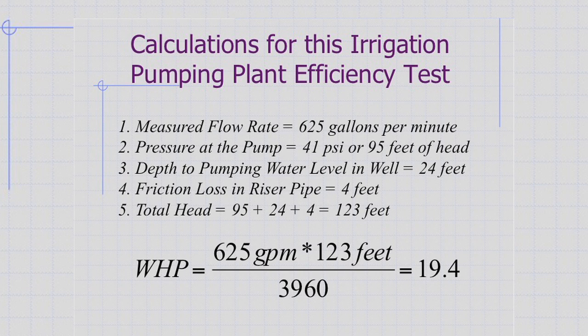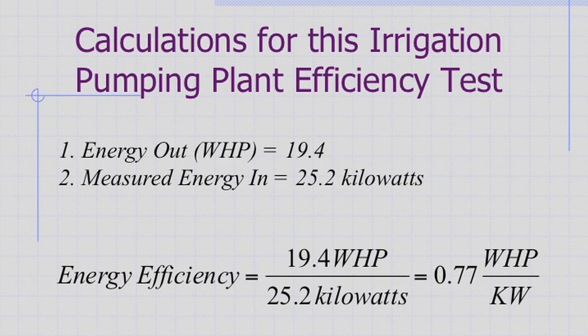The depth of the pumping water level in the well that we measured was 24 feet, and we estimate the friction loss in the riser pipe is about 4 feet. So if you add those up, the total head is 123 feet. We multiply that times 625 and divide by the constant 3960, and we see that the water horsepower is 19.4. So that's the energy out. Then we measured the energy in by reading the electric meter, and the energy in was 25.2 kilowatts. When we divide 19.4 water horsepower by 25.2 kilowatts, we end up with 0.77 water horsepower per kilowatt.